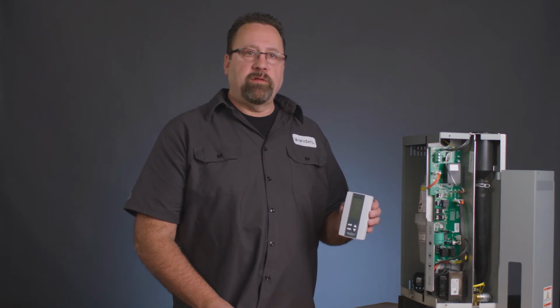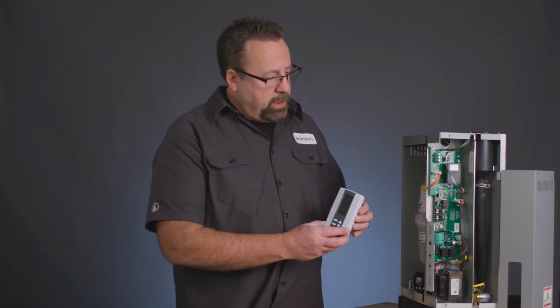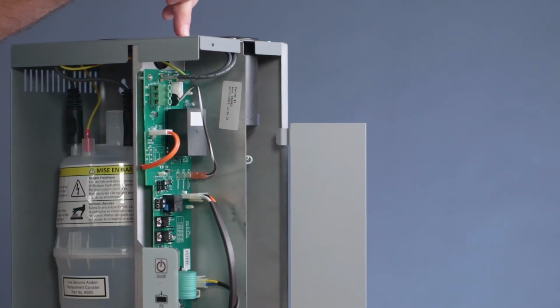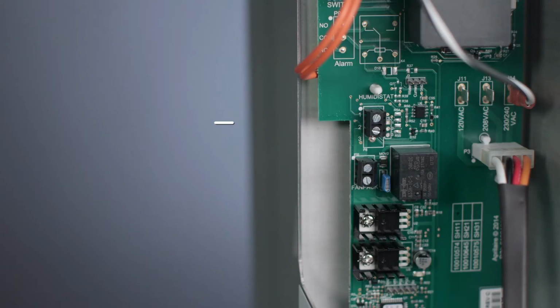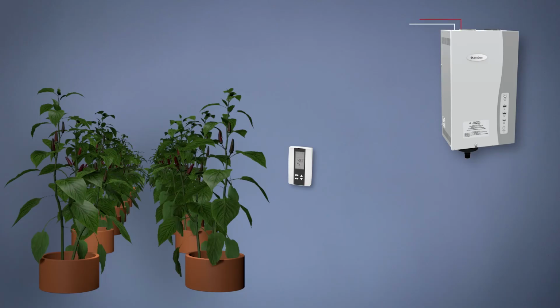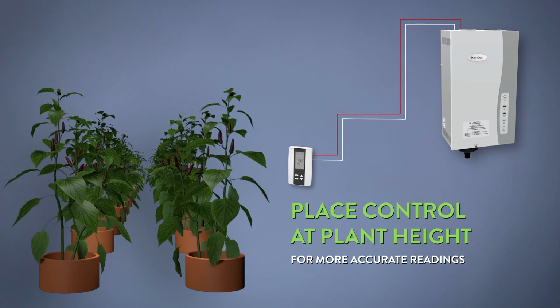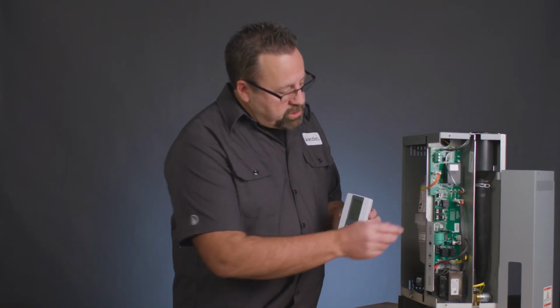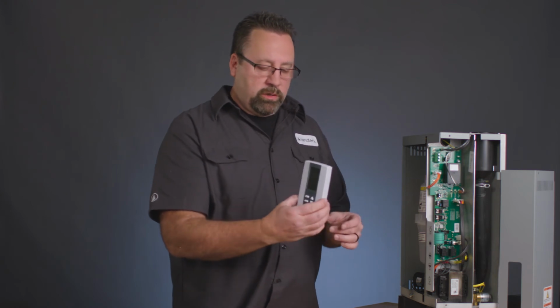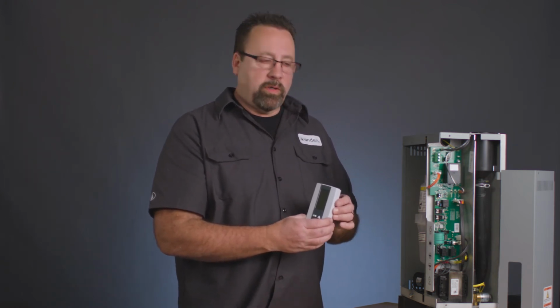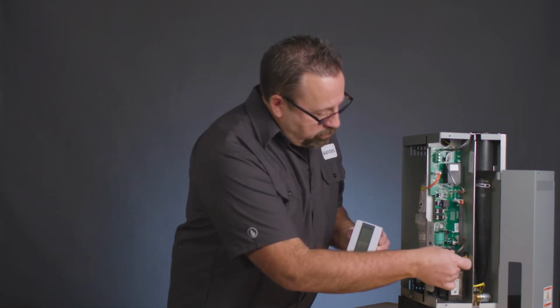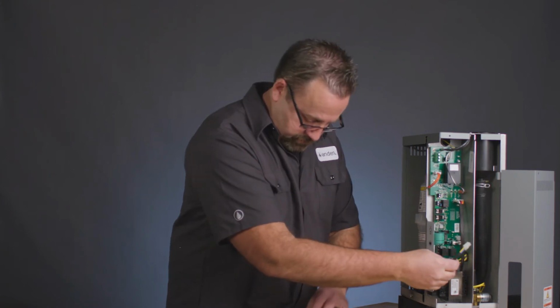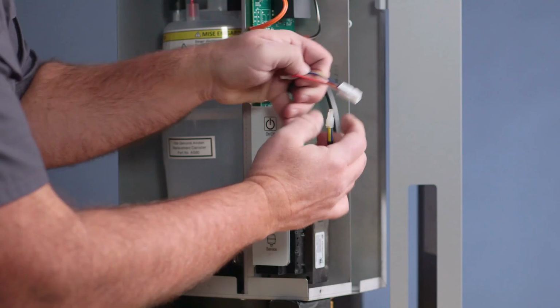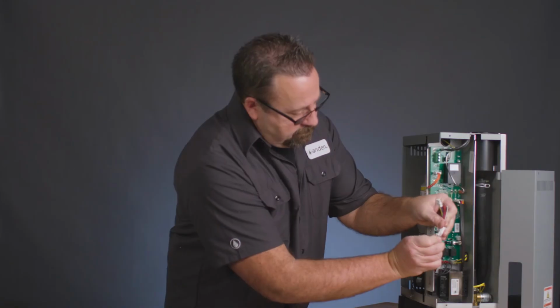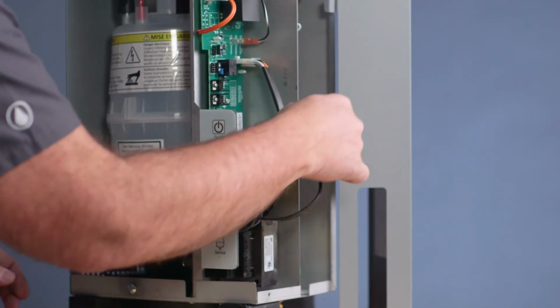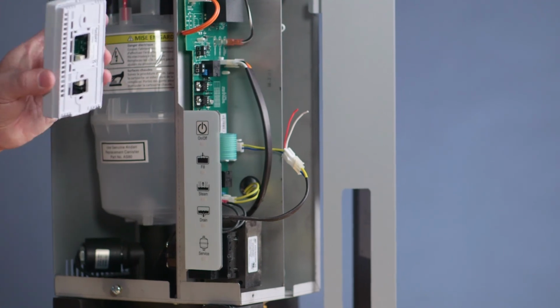The Aprilaire steam humidifiers come with the model 5558 control. This control gets wired and powered from the steam humidifier itself. The low voltage wire comes in through here and connects right to these terminals, and then also connects to the humidistat that will be down at plant height in a grow environment. Thermostat wire will connect from the humidistat terminals and go directly to the control. And we'll also power this control from the steam humidifier. The transformer wire right here can be simply unplugged, and we send this little jumper along with it. And that gives us 2 bare wires to use to get 24 volts to power the control.